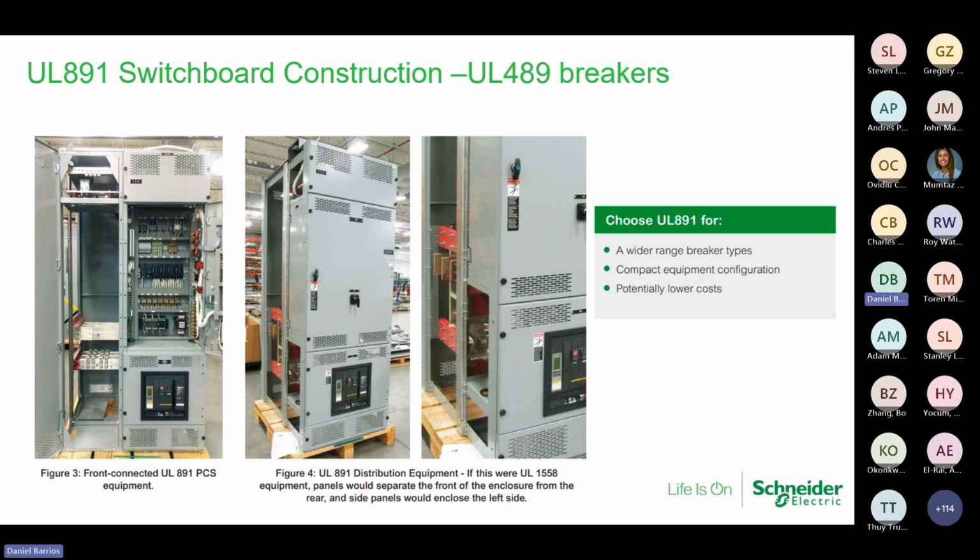With manual breakers, we can stack up to 4. With electrically operated breakers, we may be limited to 3, depending on their ampacity, in order to house the controls and the switches and such. While we're on that subject, if you're writing your specification, do you want an energy reducing maintenance switch, ERMS system? Do you want that? If so, please clarify that to us. Do you need it individually? Or can we have one switch that puts all breakers in that situation should you be in a maintenance mode or such?